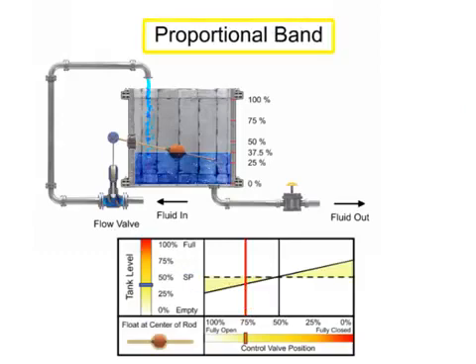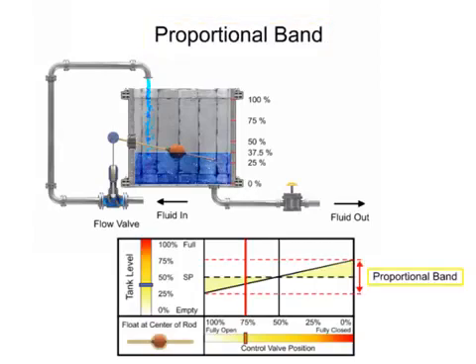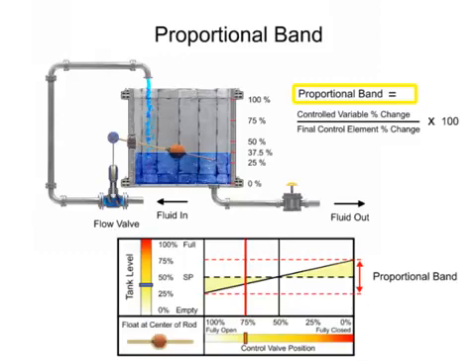Proportional band is defined as the percentage of change in the controlled variable which causes the final control element to go through 100% of its operating range. Proportional band is calculated by dividing the controlled variable percent change by the final control element percent change, multiplied by 100.